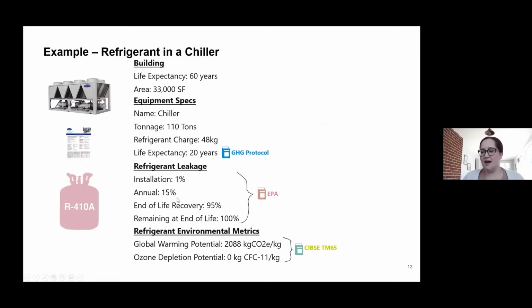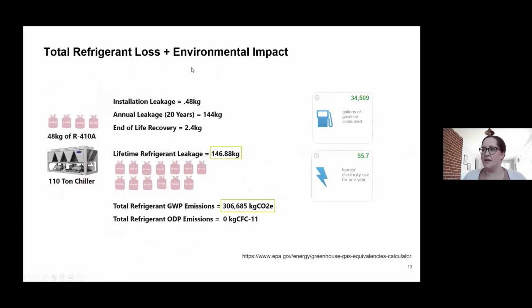The leakage statistics on this per the EPA guidance is that when you install it, you leak 1%. Every year, it's going to leak 15% according to the EPA. At end of life, you would lose 5% as you're taking the system apart, and you would assume that it was completely topped up at end of life. So the end of life remaining is 100%. And then the environmental metrics around this, which we reviewed before, are 2,088 kilograms CO2 per kilogram of refrigerant. So if you look at how much actually leaks from the initial charge of 48 kilograms, you're losing a lifetime amount of 3 times that.